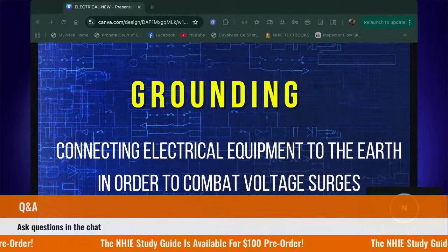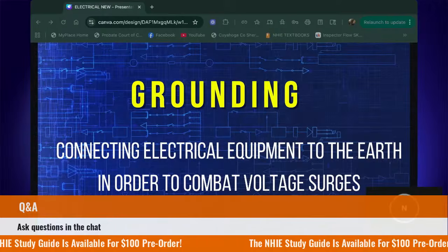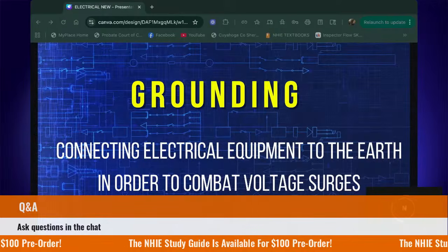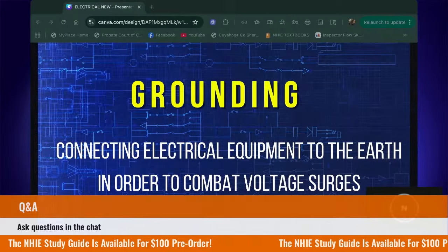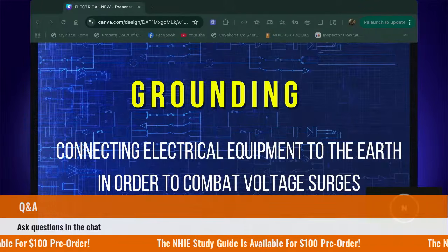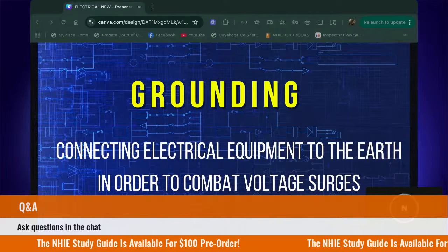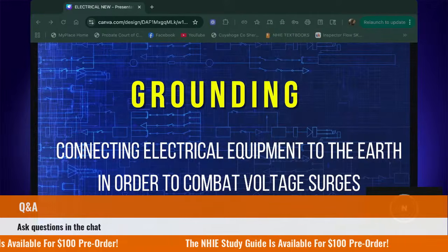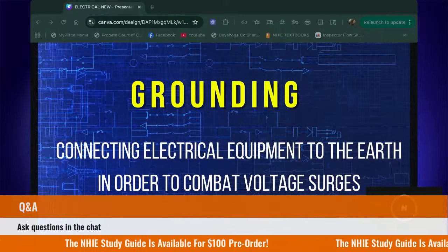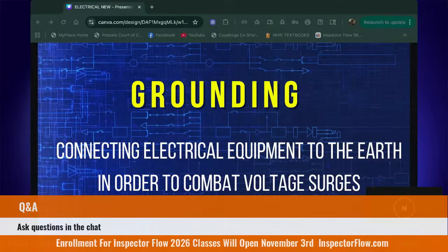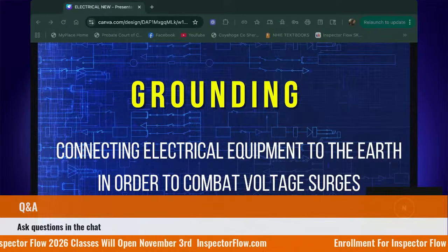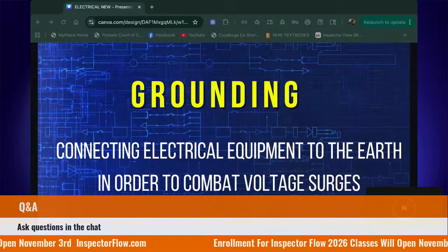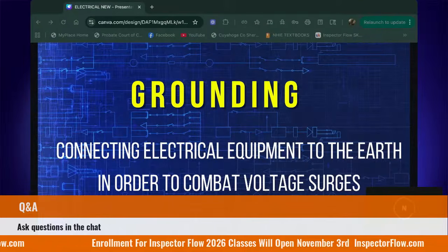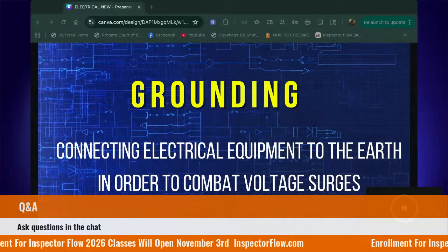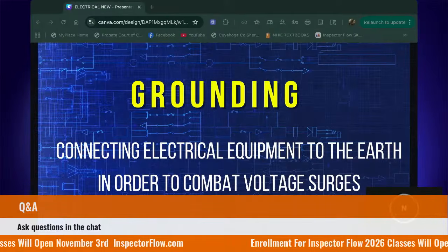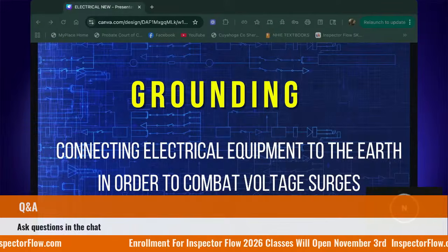Now, there are 2 ways that grounding works. We have system grounding, which is done at the main panel. This is the main connection between the wiring system of the house and the earth. So system grounding is again the entire system. I can't get into that right now. And then we have equipment grounding, which is grounding for our circuits.